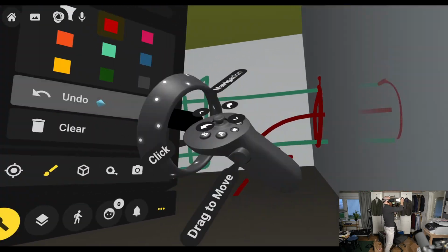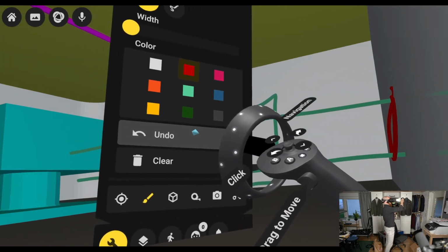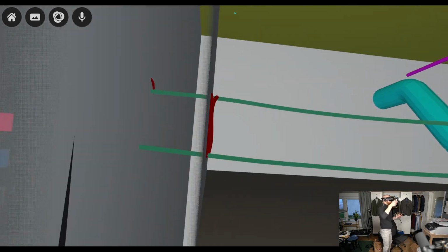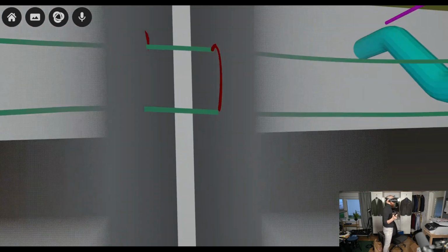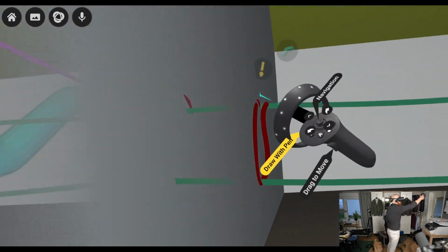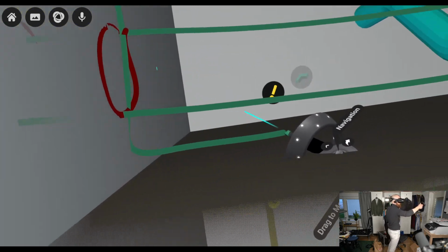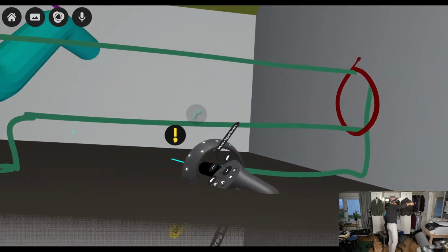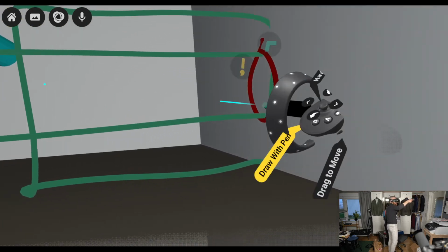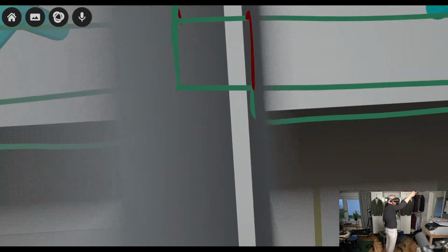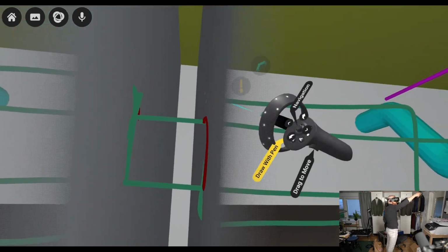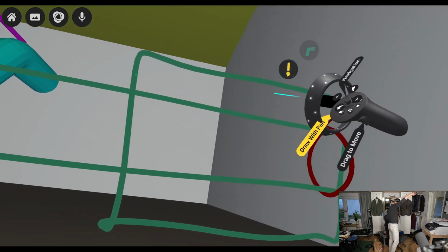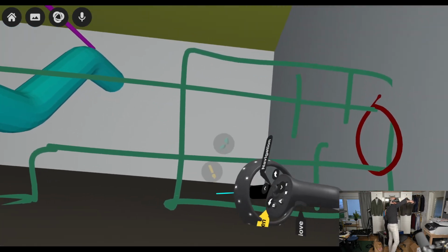Well, let's do a series of undos here. And get rid of the other silencer as well. What you should do, if you want to do it as good as possible, is that you should place your silencers here, flush to the wall. And if you do it on both sides, you can get a really good insulation. If you have very high requirements, this might be what you have to do. Both sides. It could be enough on one side, but you have to check it out case by case, because all the parameters affect each other.